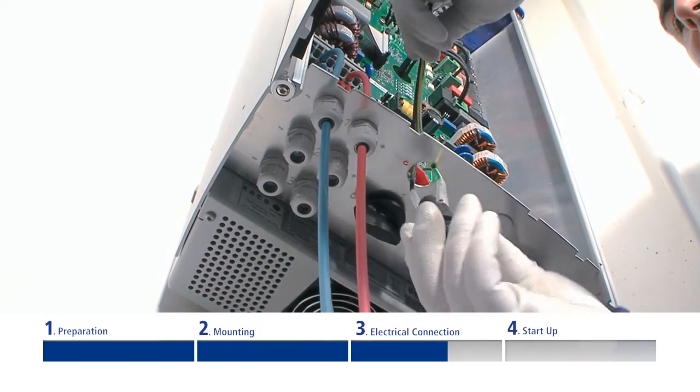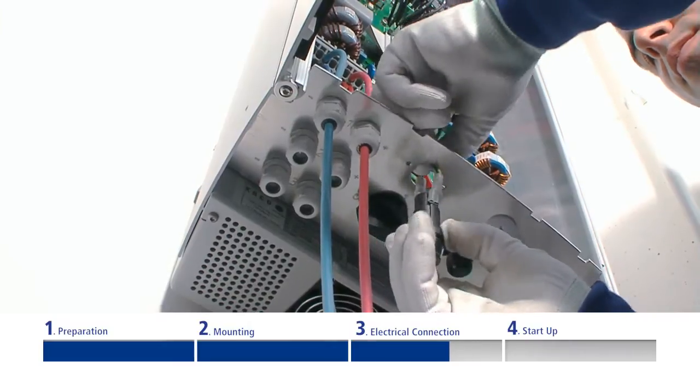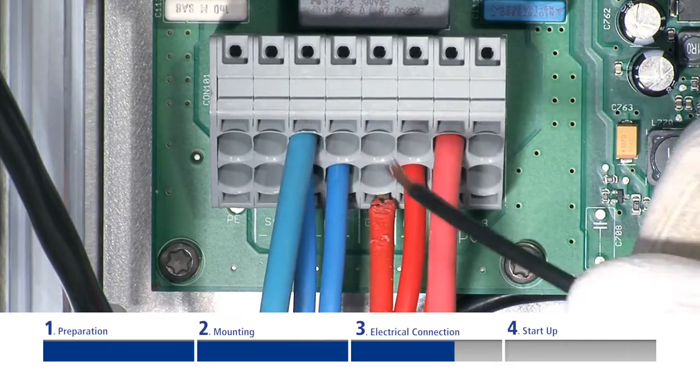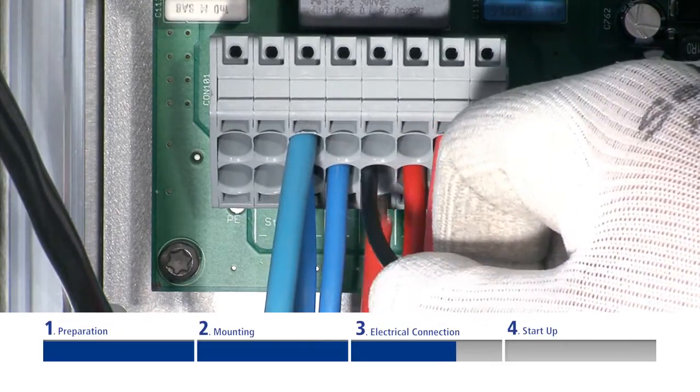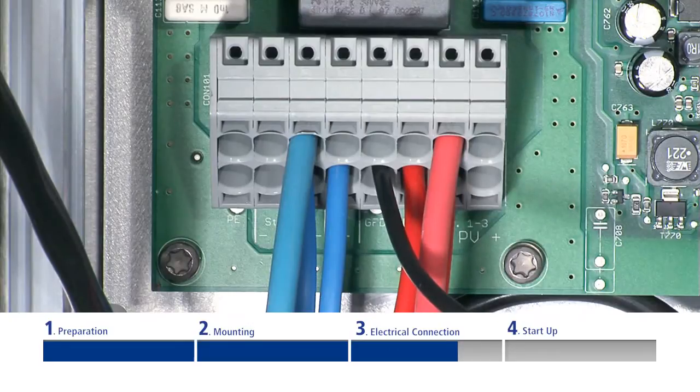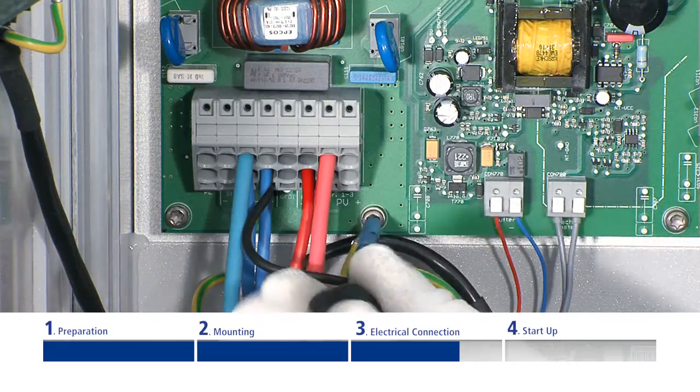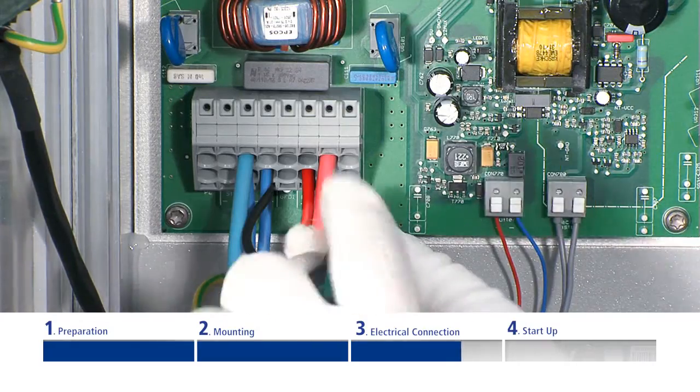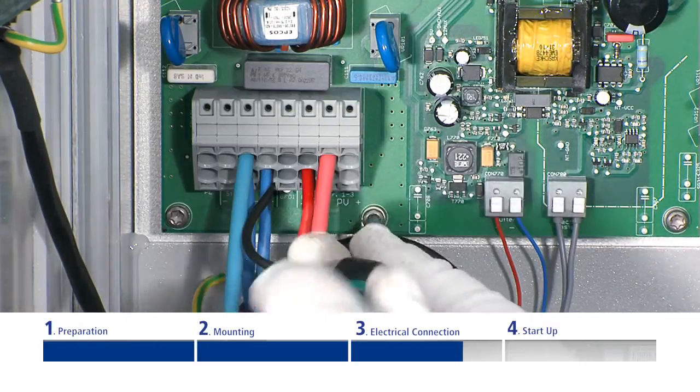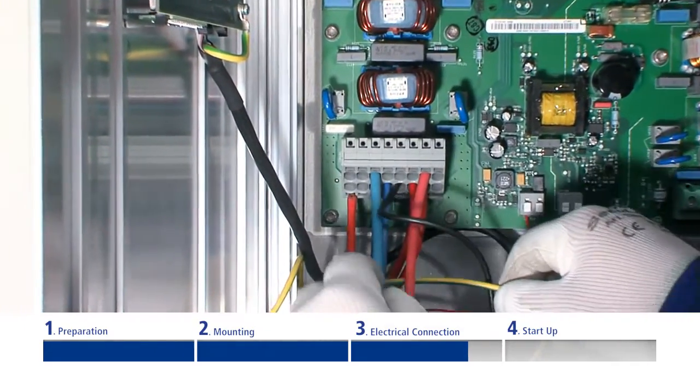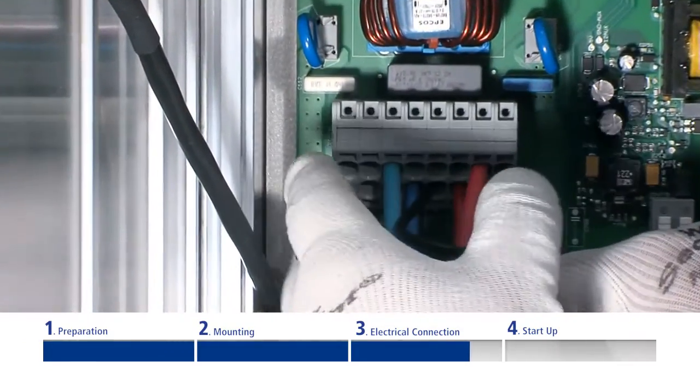Use a screwdriver to remove the cover of the fuse holder and attach the fuse holder using the screws provided. Connect the black cable to the bottom DC terminal labeled GFDI. Attach the PE cable, green-yellow, to the corresponding PCB fitting using the cable shoe or depending on the model directly into the PE terminal on the PCB board.